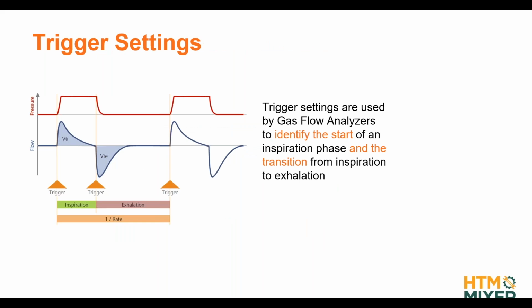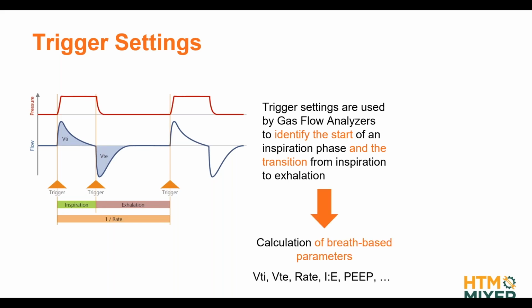That's called trigger settings. Okay, so gas type and gas standard are important for the measurement of flow and volume. Trigger settings are used by gas flow analyzers to measure the so-called breath-based parameters, such as the tidal volume, inspiratory and expiratory tidal volume, respiratory rate, I to E ratio, and PEEP, for example. These are all parameters that somehow depend on the breath phases, right?